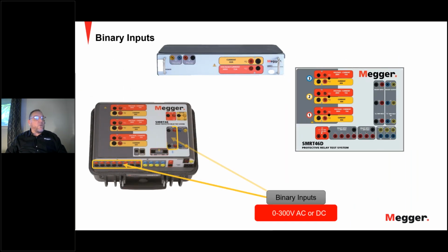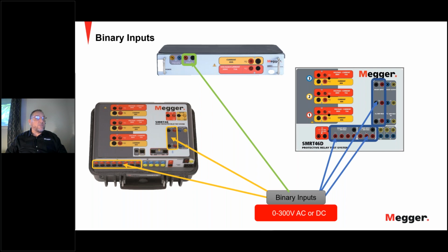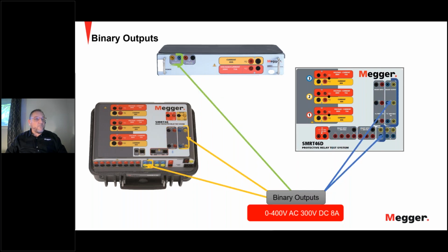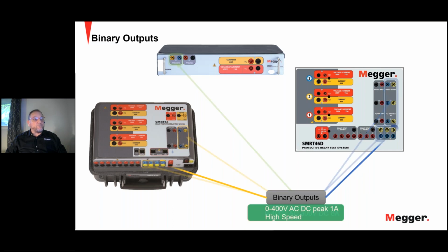The next step is your binary inputs. Each unit comes with one, in the case of the SMRT1, or more binary inputs with a voltage rating of 0 to 300 volt AC or DC. You get up to 4 8-amp binary outputs and 2 1-amp high-speed binary outputs that can be provided as well. And this, again, is dependent on what unit you are working with.